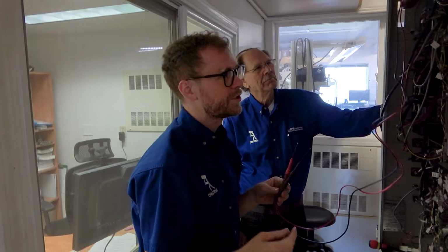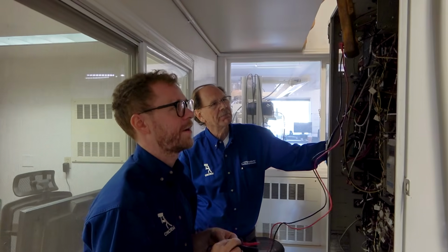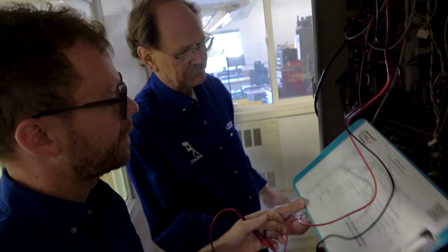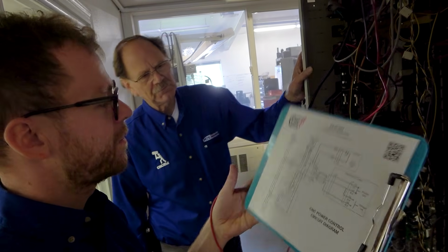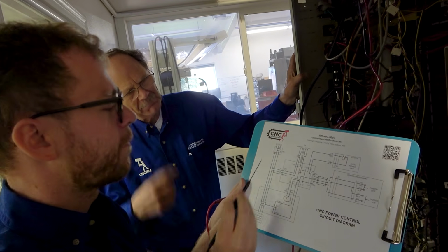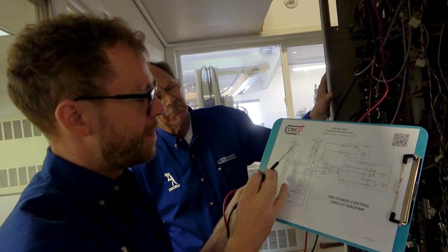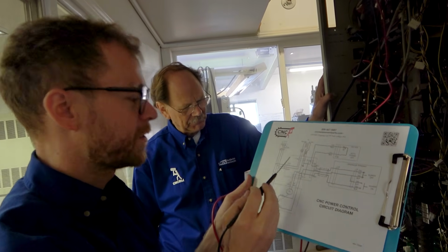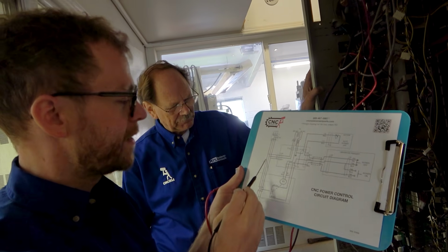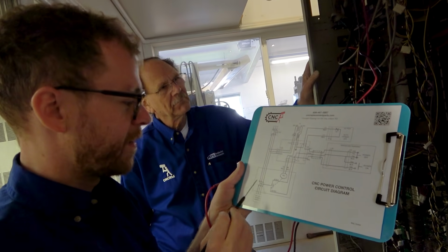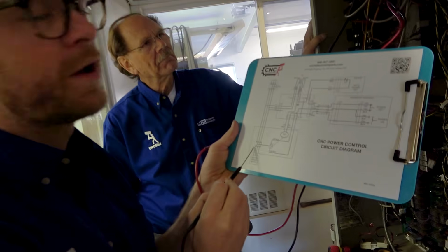The next thing to check is the top of the contactor. So this is the main contactor right here that turns this whole machine on. So if we're working our way down the drawing, we've checked the main incoming power on the top of the breaker. We've checked the bottom of the breaker. This is the symbol of the breaker, and it's closed. Now we work our way down, and now we're going to check right here. This is labeled as the K1 contactor. Now the K1 contactor is right here.